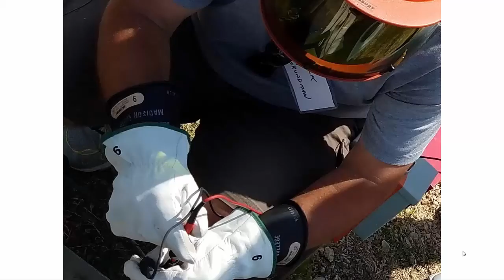Why is our prediction for that electrical cable 0 volts? Everything is wired together. It turns out that for safety purposes, microinverters will not permit electricity to be produced until connected to the grid. The microinverters have to see a grid that they'll be connected to. And indeed, our measurement here is 0.